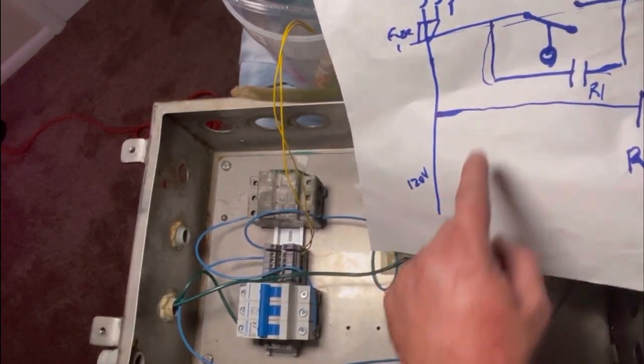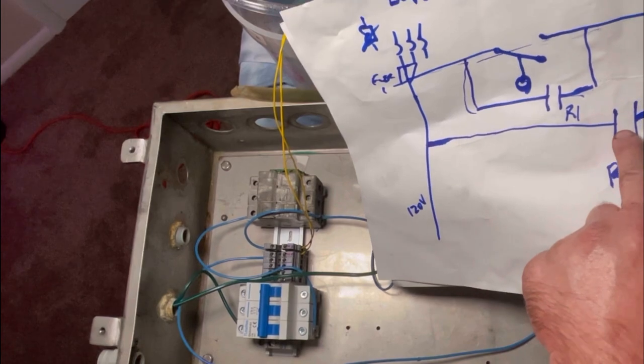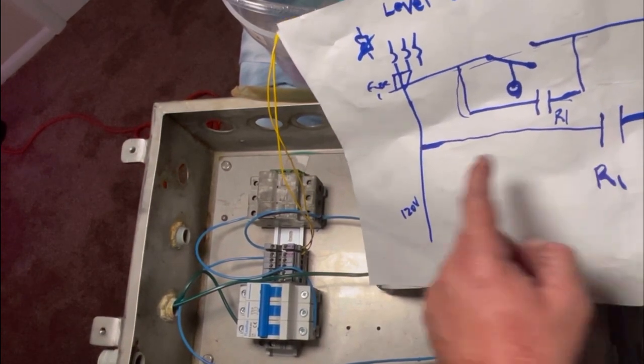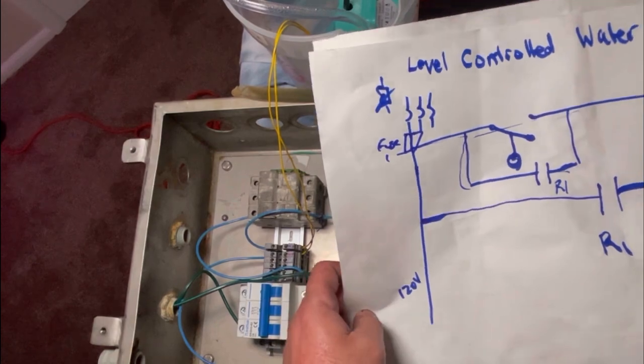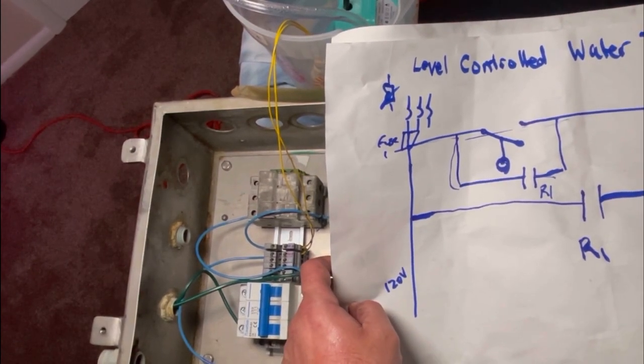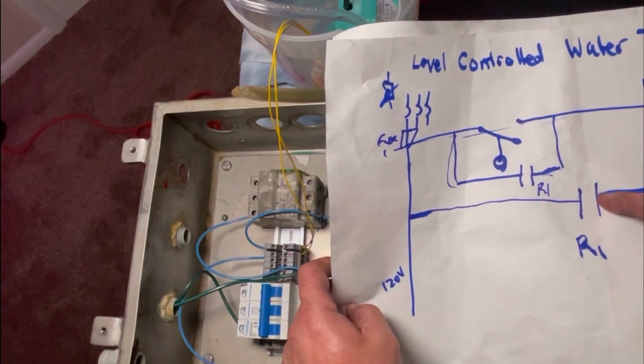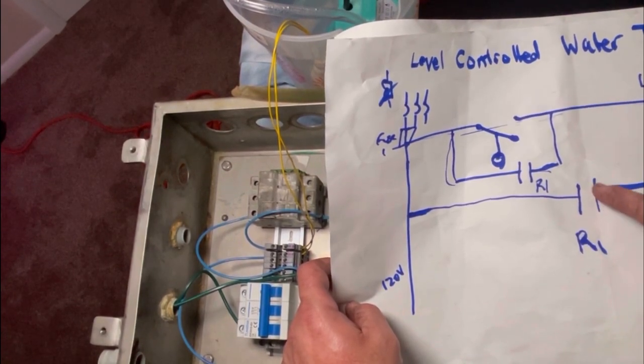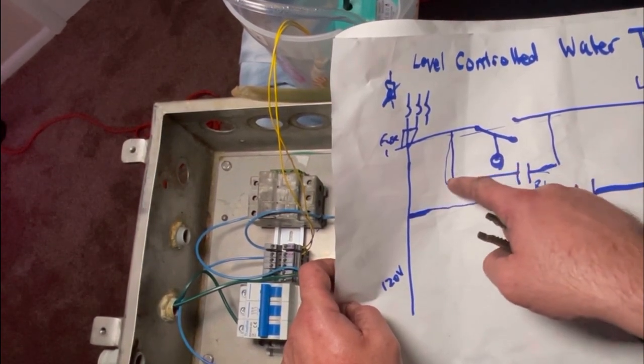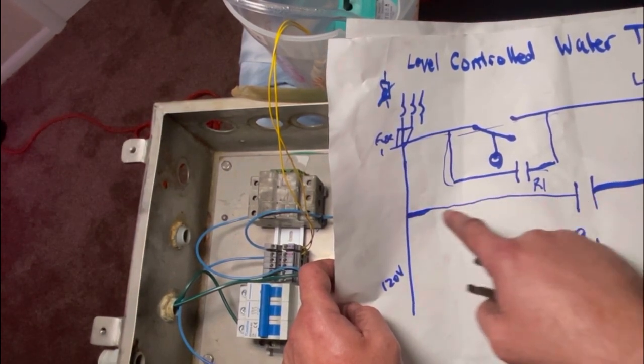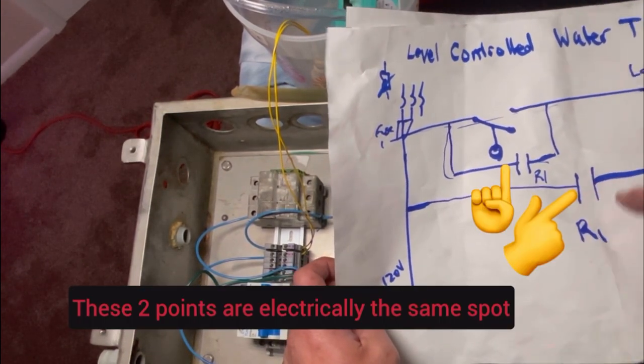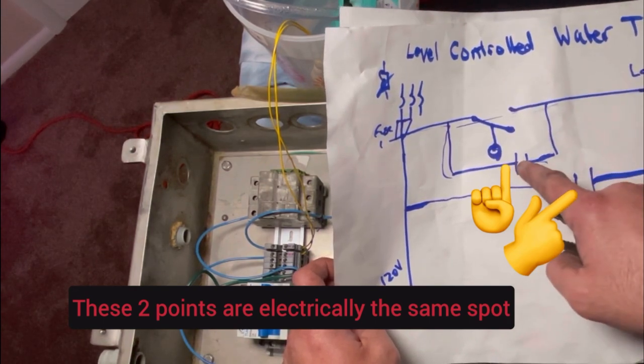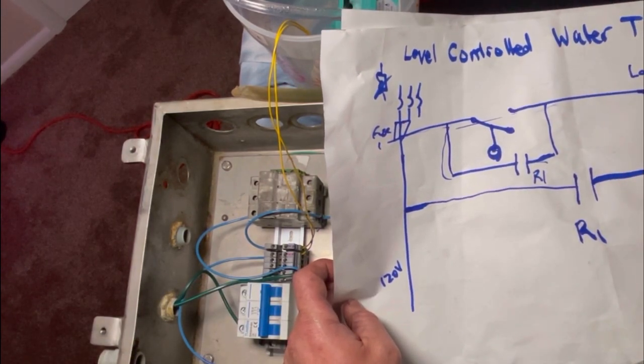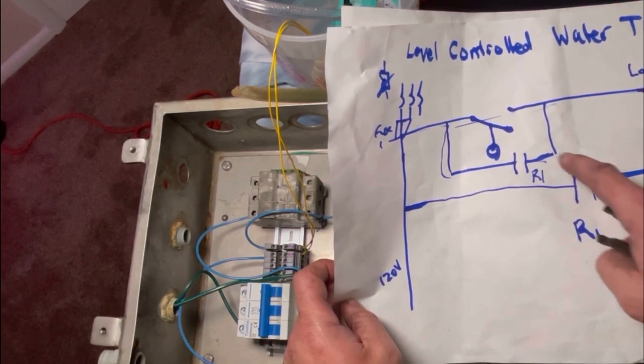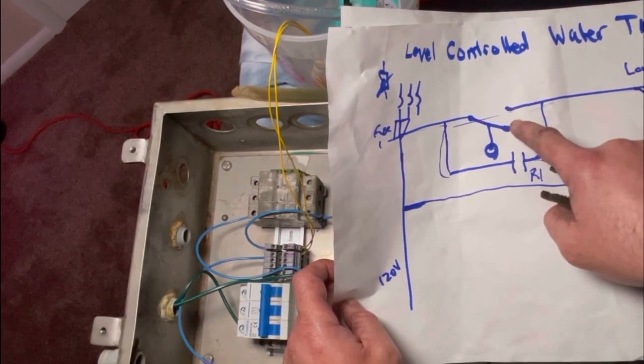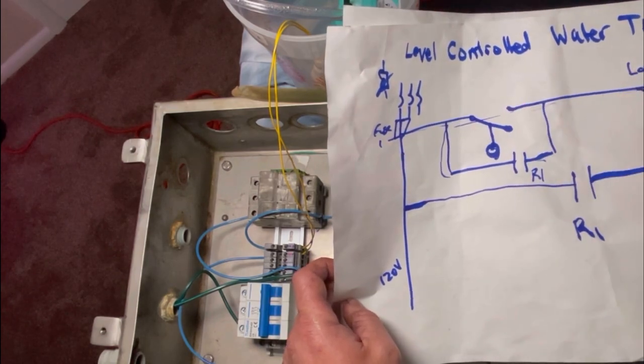So this set of contacts on the relay, if you remember we were talking, there's like 4 different sets of contacts. We could use a different set of contacts. We probably should, but I'm just going to use the same one. I'm going to reuse this point right here as this point because technically speaking, electrically, this is all the same circuit. So we're just going to reuse that same set of relay 1 normally open contacts. And where I have that wire coming out to feed that pump, I'm also just going to run that up here on the output side of that first float.